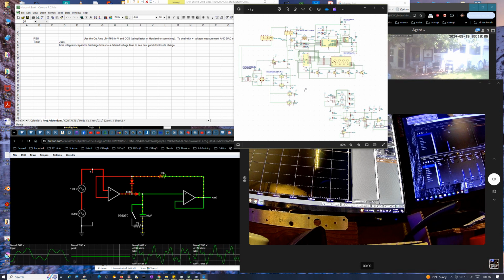But something like this is a shunt meter, so it's a straight resistance - you can get a reading really fast with it. And if you had a good fast peak hold circuit that can do 1 millisecond or less transients, you can get a good idea of what that is.